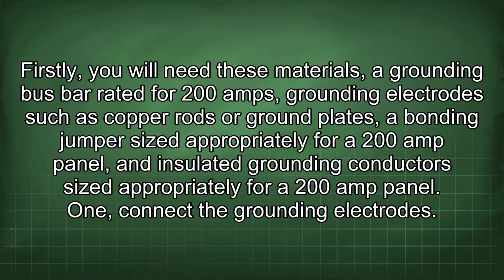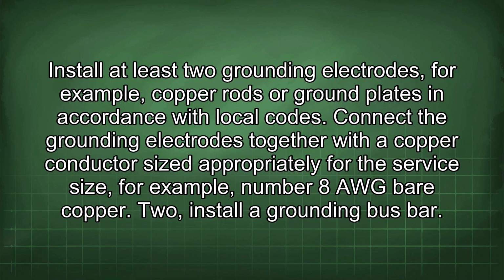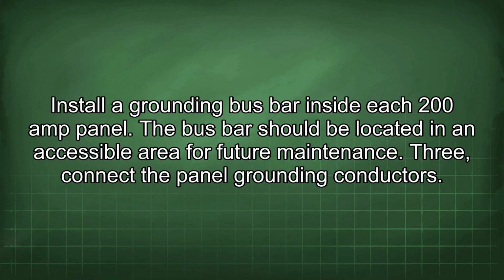1. Connect the grounding electrodes. Install at least 2 grounding electrodes, for example, copper rods or ground plates in accordance with local codes. Connect the grounding electrodes together with a copper conductor sized appropriately for the service size, for example, number 8 AWG bare copper. 2. Install a grounding bus bar. Install a grounding bus bar inside each 200 amp panel. The bus bar should be located in an accessible area for future maintenance.